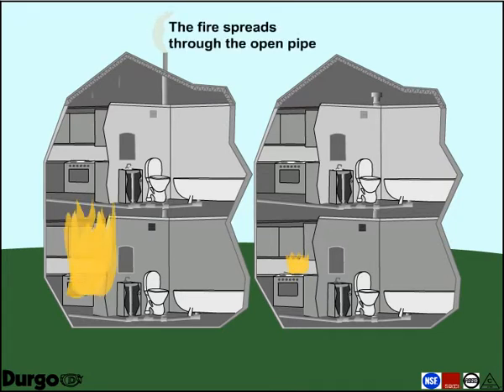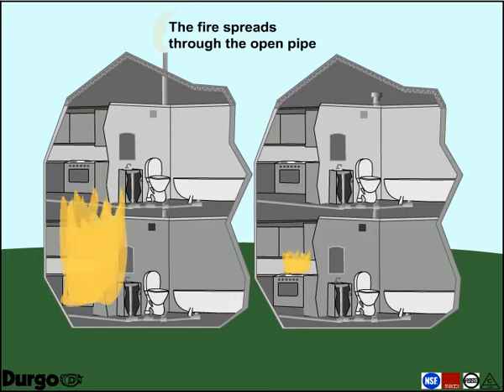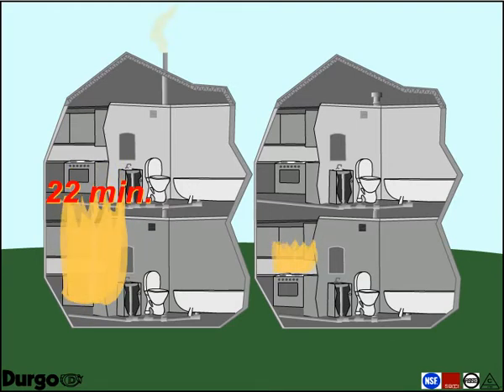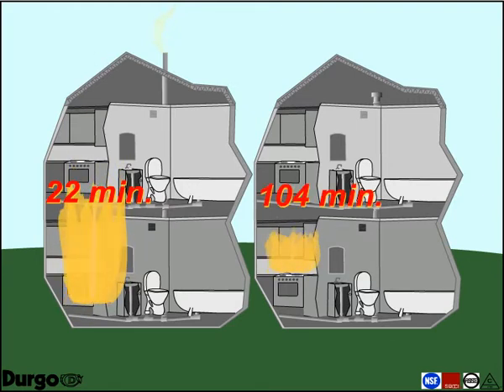In Test House 1, the fire had spread to the second floor through the open pipe in 22 minutes. In Test House 2, utilizing the Durgo air admittance valve, the fire took 104 minutes to spread to the second floor.